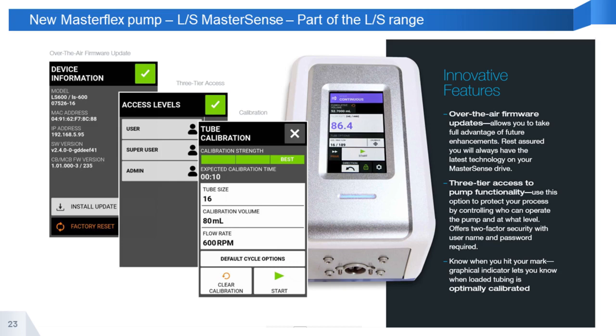And then another feature would be calibration strength. This is a great feature that gives the user live feedback on the strength of the pump calibration. A good analogy to explain this feature would be the software used within a password. If you don't use enough letters, numbers, or symbols when setting up a new password, the software would advise you that the password is weak. The pump does the same function here. If the calibration is outside of our advised tolerances, if you're not dispensing enough volume within the calibration period, the pump would advise you that the calibration is weak, strong, or the best possible parameters.